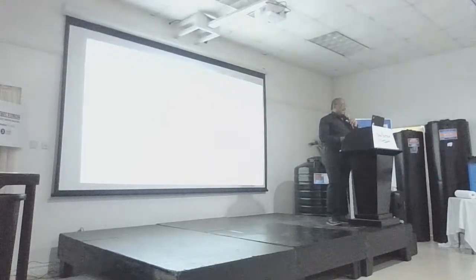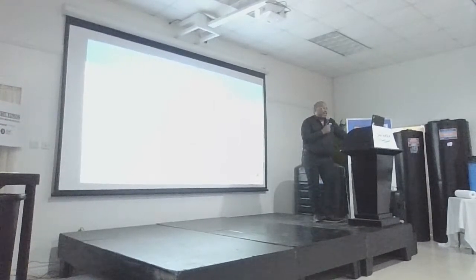Right. So secondary treatment units, prefabricated units which we manufacture, can be used where some of these conditions before can't be met. If you have clay or sands, the groundwater is too close, or like my example, even Otabor where it was hard bedrock, so they couldn't do a soakaway. High water table, or just prone to flooding, and so that they, as the example I gave, they would just fail.